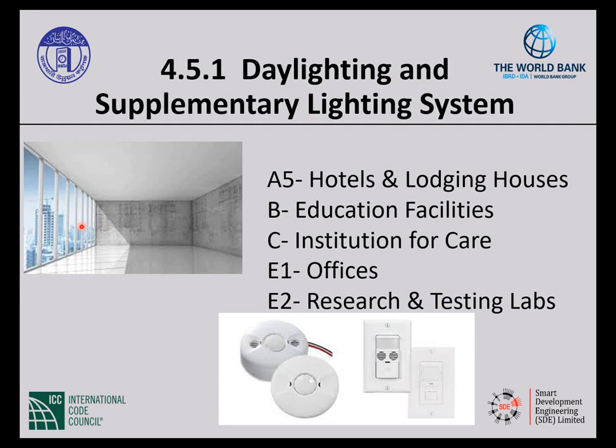So 4.5.1.3 says for buildings of occupancies A5, hotels and lodging houses, B, education facilities, C, institution of care, E1, offices, and E2, research and testing labs, for those occupancies, photoelectric sensors shall be connected to luminaires to enable dimming or switching off lamps that do not require to be operated because there's adequate daylight.